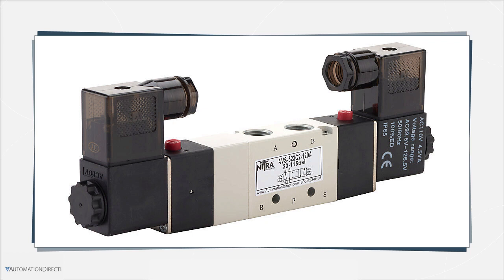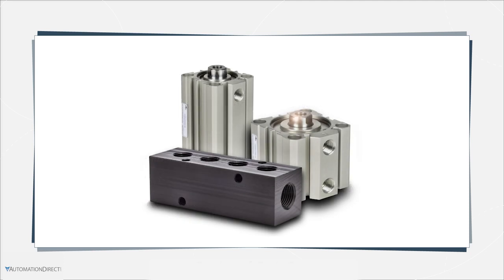The difference in pressure on the two sides of the piston results in a force equal to the pressure differential multiplied by the surface area of the piston. If the load connected to the rod is less than the resultant force, the piston and rod will extend and move the machine element.